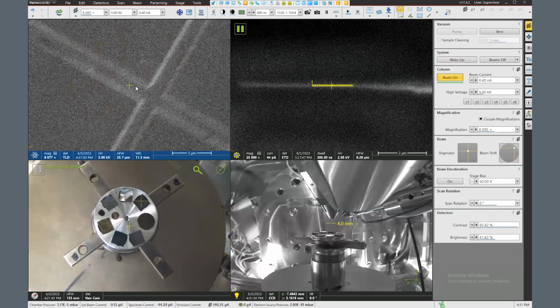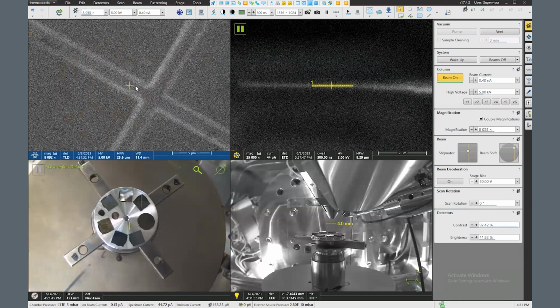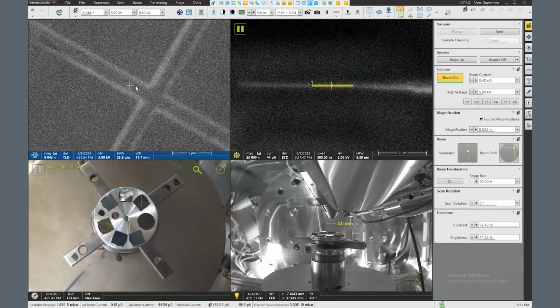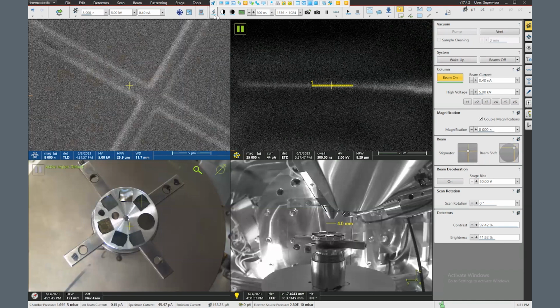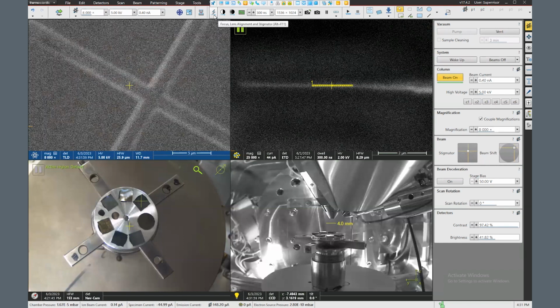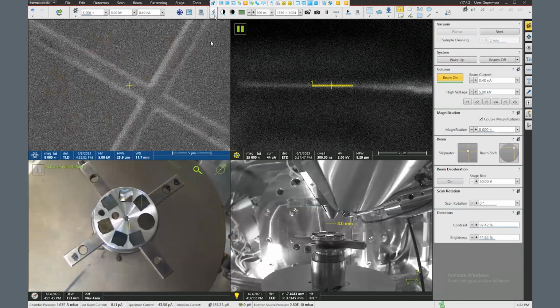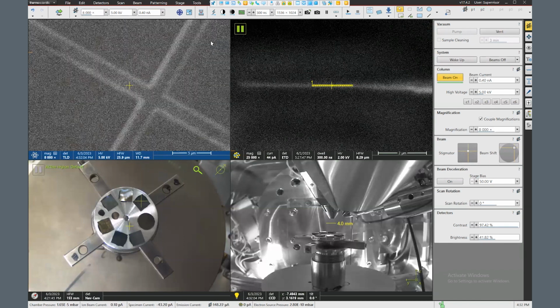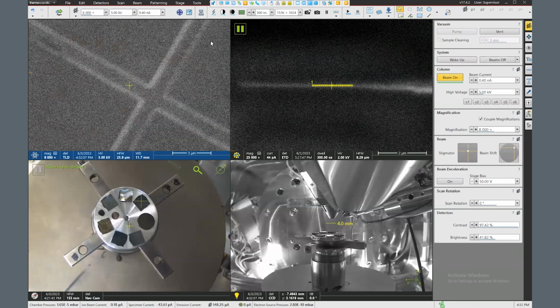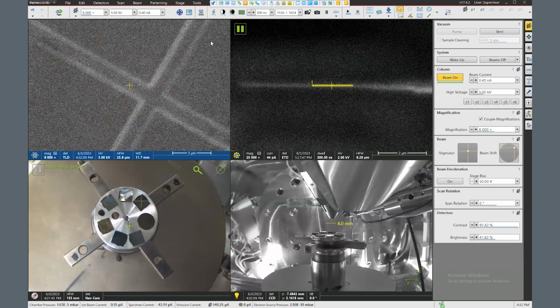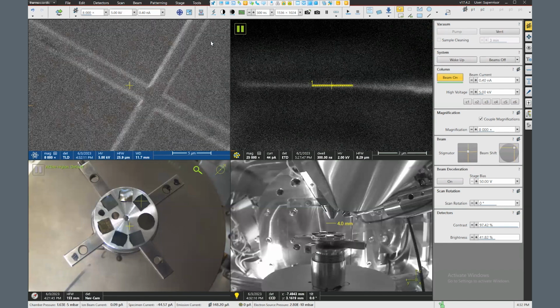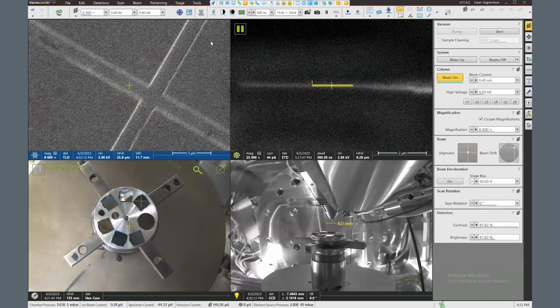If I do this, you'll notice there's stretching going on. This is indicative of stigmation. Normally the flash would take care of stigmation for us, but in this particular case, the algorithm didn't work real well. So we're going to go to the MUI knobs. You have stigmation X and stigmation Y, and we're going to see if we can't get this a little bit sharper.